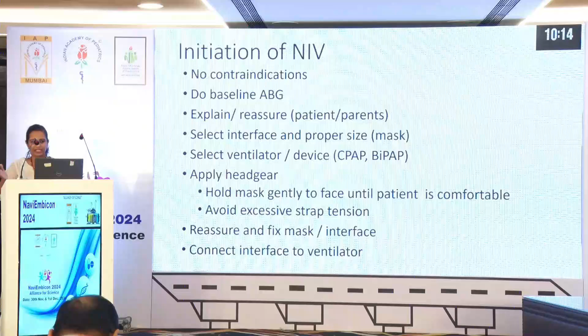You will apply the headgear. You will hold the mask gently to his face and make the patient comfortable. You will not tighten the straps initially. Then you will connect the interface to the ventilator. Whenever the interface is applied, it has to be gently applied without fastening the head straps. You provide constant reassurance. When you start, you always start with only the expiratory positive airway pressure.